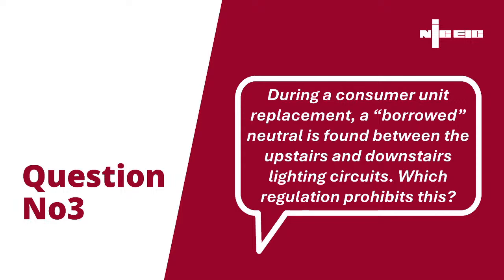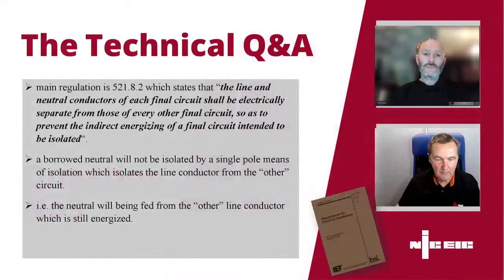So they asked, and our advice to them was simply that the best regulation is there on screen now. We're showing it, and it's 521.8.2, which states that the line and neutral conductors of each final circuit shall be electrically separate from those of every other final circuit, so as to prevent the indirect energizing of a final circuit intended to be isolated. So the situation with a borrowed neutral would mean that you may feel that you've isolated the circuit, but because that's borrowed, it's also supplied from another circuit, then it means your neutral won't be isolated.